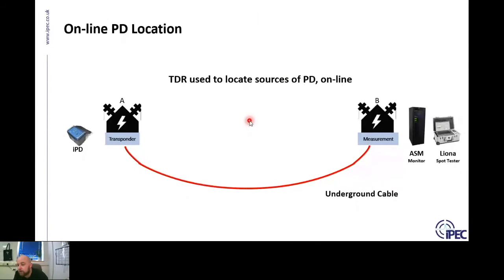Okay, so next I'm going to discuss how we locate PD online - how we do location of PD on an underground cable whilst it is live. The way we locate on an underground cable is on the other end of the cable. So this is our measurement point, this is where our monitoring system or test equipment is installed.